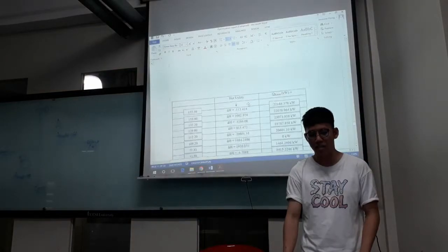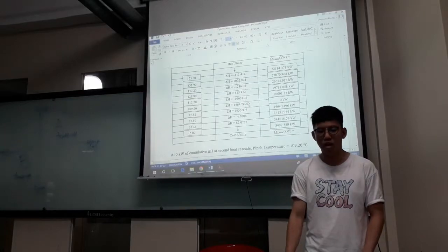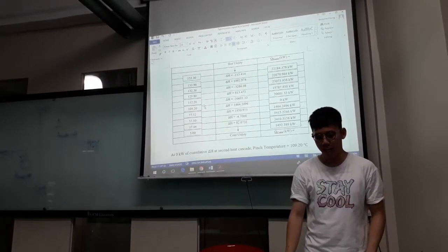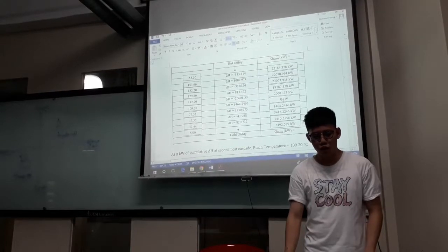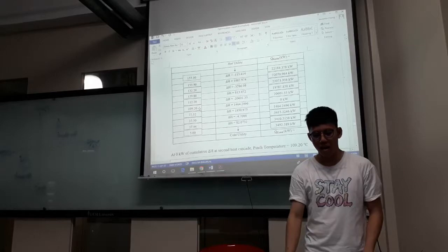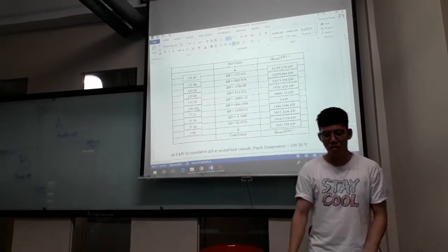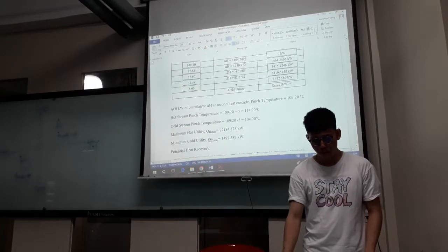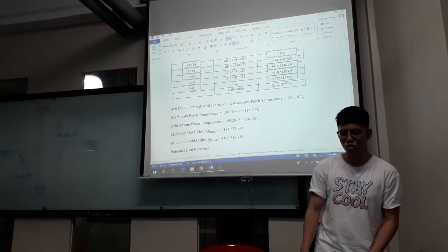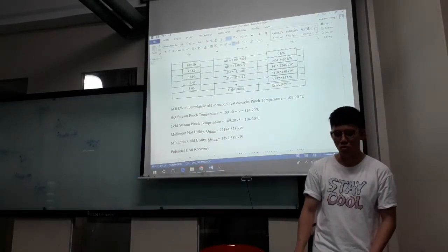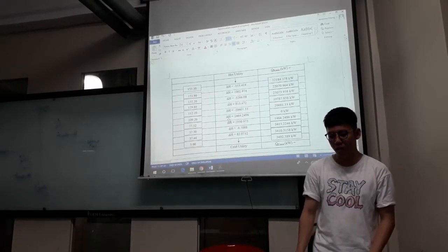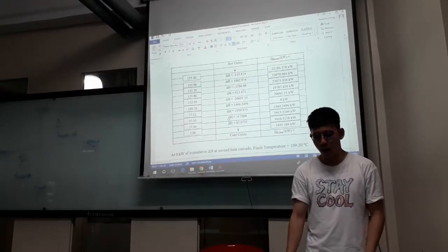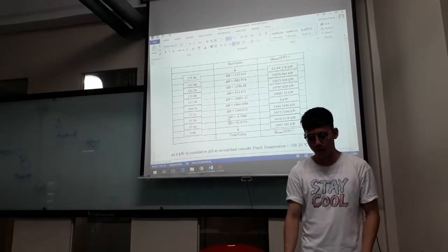The largest heat deficit will be used as the starting heat input in the second heat cascade table. From the result of this second heat cascade table, the zero energy point occurs at a temperature of 109.20°C. This will be our pinch temperature. To obtain the hot pinch temperature, we add 5°C to get 114.20°C. For the cold stream pinch temperature, we subtract 5°C and get 104.20°C. The hot utility calculated from this table is 22,184.378 kilowatt, and the cold utility is 3,492.589 kilowatt.